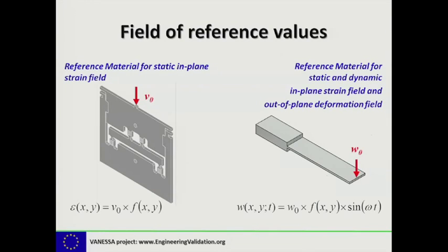Here are two exemplars of how to provide a field of reference values. On the left you see a reference material for static in-plane strain fields, whereas on the right you see a reference material that can be used for static and also dynamic in-plane strain fields and out-of-plane deformation. The idea is that you express your displacement value w or strain value epsilon as a function of x and y across the gauge area, and relate those to a simple factor of v0 or w0, which is the measured displacement of the top on the left or the measured displacement at the tip on the right, relating it to a field of values f(x,y) describing the strain or deformation. On the right you also have a sinusoidal term for the dynamic use of this material.